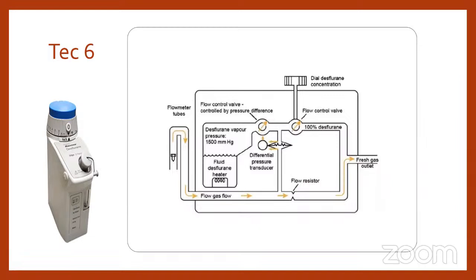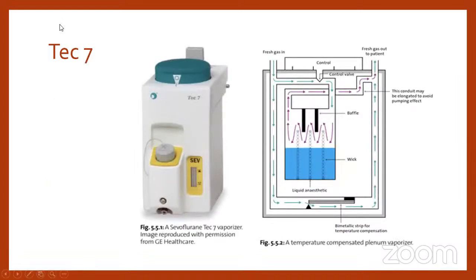It is again a safety mechanism in which, if the gas flow is high, it limits the desflurane through the internal transducer system. So the amount of desflurane that is coming out of the system will remain the same. Tec 7. These are the modern day vaporizers most of us have seen and regularly use in our system. In our institute, we have these vaporizers assembled to our workstation. It is also a temperature compensated plenum vaporizer. Basically, it has different vaporizers for halothane, enflurane, sevoflurane, isoflurane.